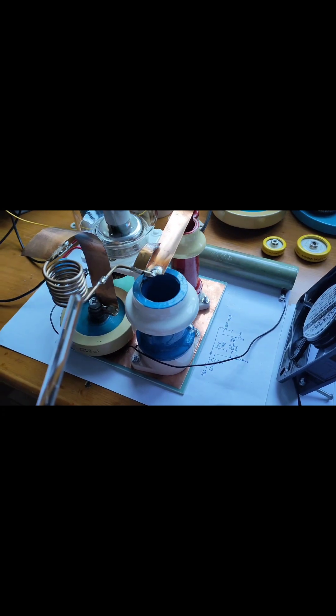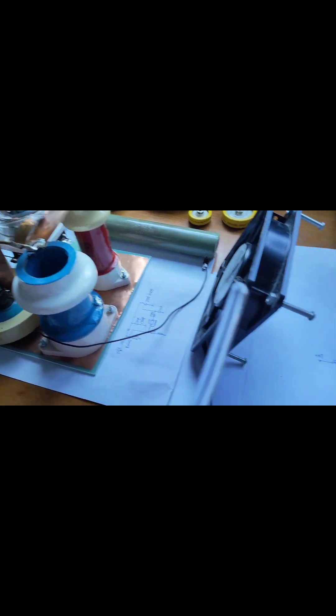This is a safety choke. In case this capacitor has a shoot-through, safety choke will short out the high-tension supply. And this is the main coil, which is located here. And the strong magnetic field inside this coil, created by the strong current induced into the coil, can generate an inductive coupled plasma.